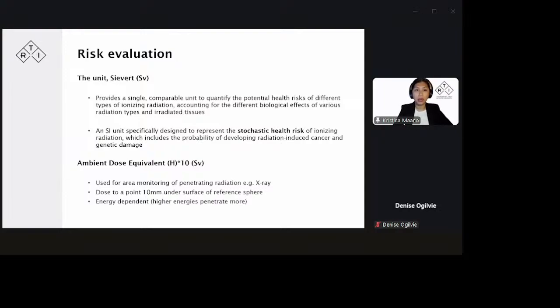And now when we do our scatter measurements, we use H*(10), which is also, of course, measured in sieverts. And this is used for the area monitoring of penetrating radiation. And the calibration is done to a dose at a point 10 millimeters under the surface of a reference sphere. And there is an energy dependence, and this is higher for higher energies because higher energies can penetrate more.